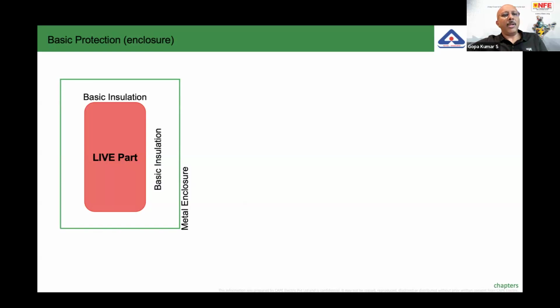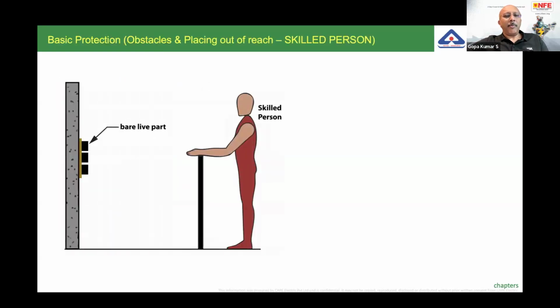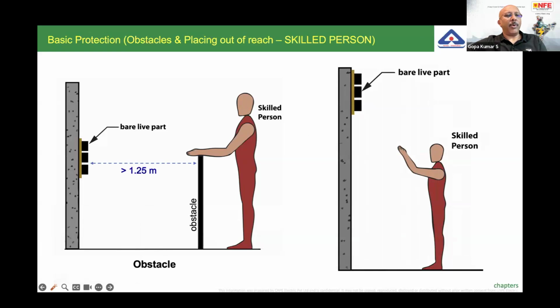Because of the metal enclosure, people don't go and touch the live part. This is an example of a basic protection. Similarly, other protective measures, for example, obstacles and placing out of reach. Obstacle means in certain applications, maybe the live parts are visible, live parts are accessible, but in between, you need to put an obstacle, and this is allowed in locations where skilled people are working. Probably this kind of installation is required in industrial premises.